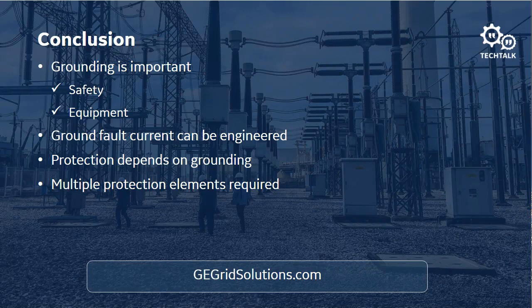Okay, let me take a look here. What should the CT ratio be of a zero sequence CT for sensitive earth fault in a low impedance system? Should it be the same as a phase CT? Okay, so for a low impedance system, it definitely should not be the same ratio as the phase CTs, because they're doing two different things, right? The phase CTs are protecting for a phase fault, which is going to be significantly higher than an engineered ground fault in a low impedance system, whereas the zero sequence CT is going to be detecting ground fault currents only for phase to ground faults, which are much lower level.